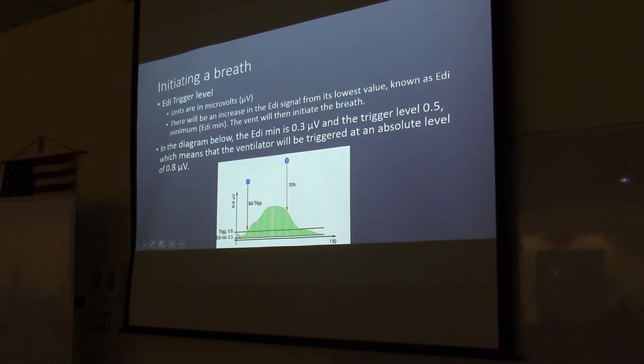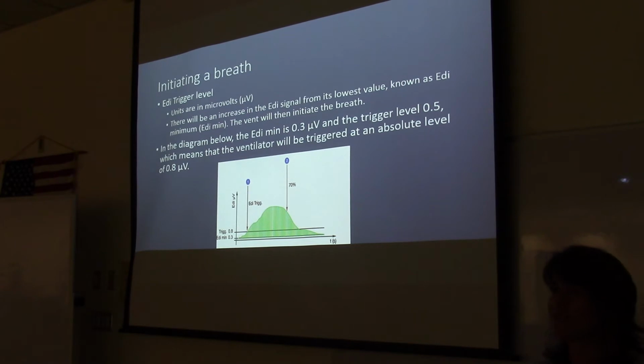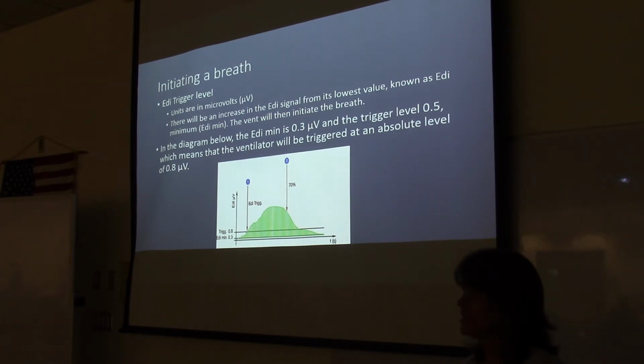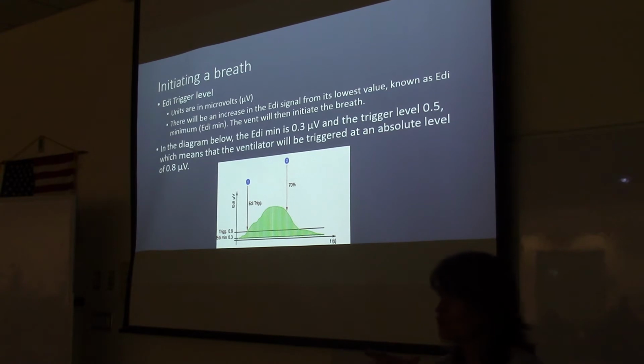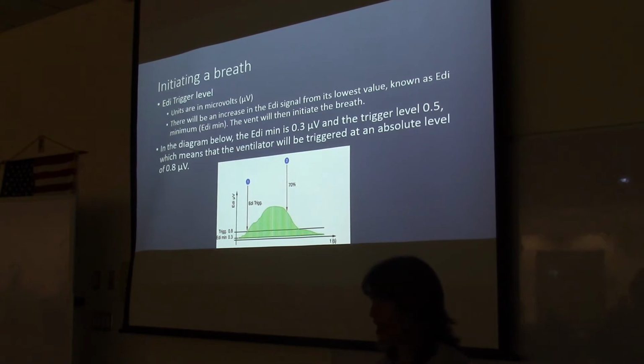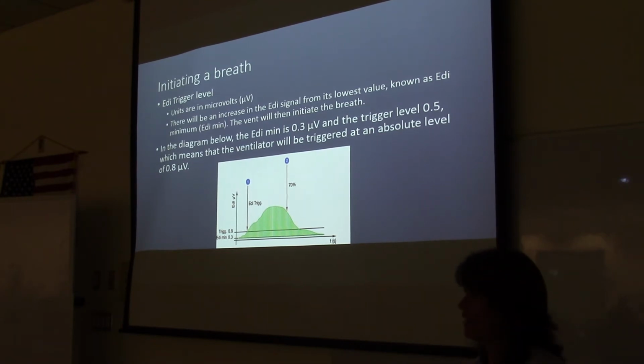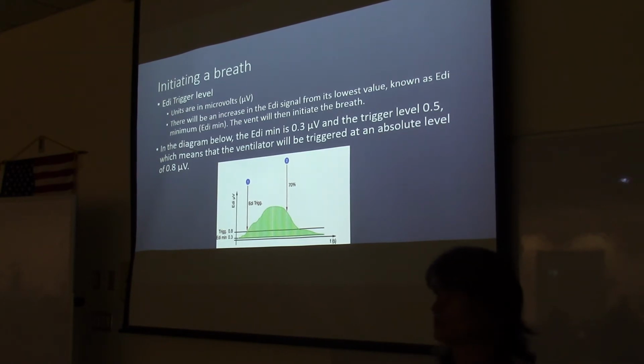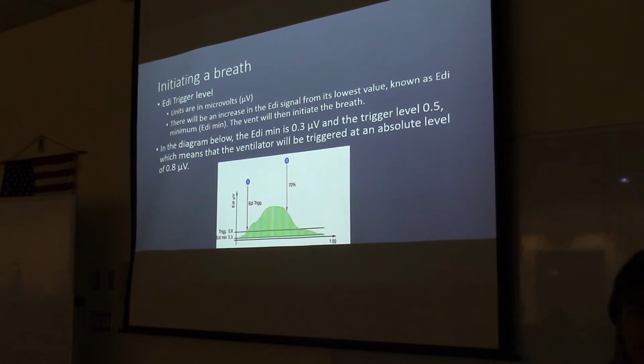There's always a little bit of an electrical signal going to the diaphragm. It's not like during exhalation there's no electrical activity. There's always a little bit of activity, and we have to know how much that little bit is. It's kind of like the background noise, and we need to avoid that. We don't want to give a breath because we'd be giving all these extra breaths, and that's not inspiration. So first we have to figure out minimum activity, that normal background noise, and set the trigger above that. So once the trigger goes above that minimum noise, we know that the diaphragm is being innervated for a breath.